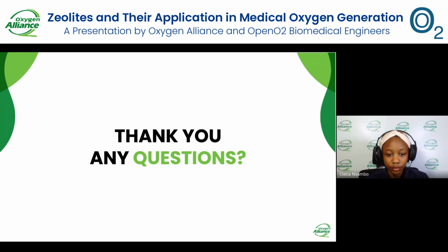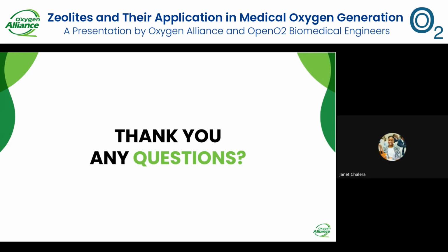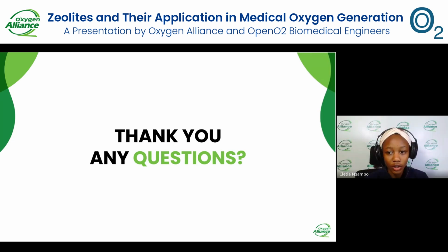We have another question. It says, in case the zeolite is found in no good performance, do we need to change the colon or refill the tank? And also, does the zeolite have a lifespan? Can you clarify what you mean by colon? Otherwise, as I have explained, if your zeolite is not working in good condition, you may have to replace the whole sieve bed if it's a portable oxygen concentrator, or you may have to refill the zeolite. I hope that has answered your question, or you can clarify.